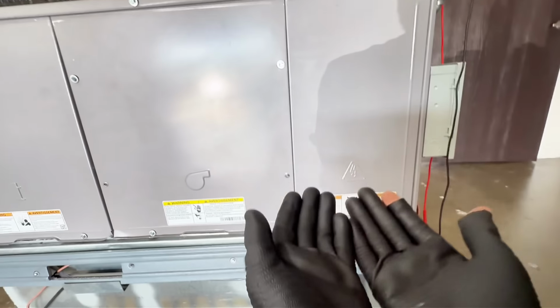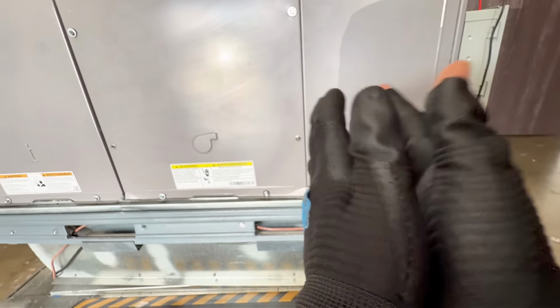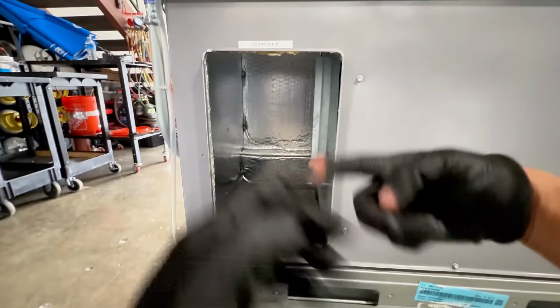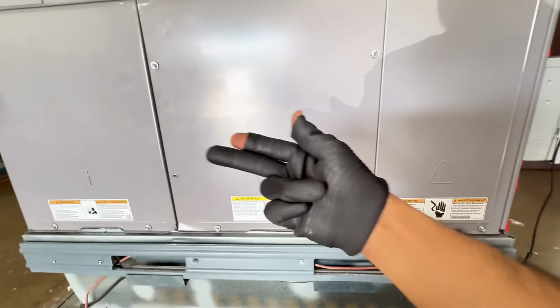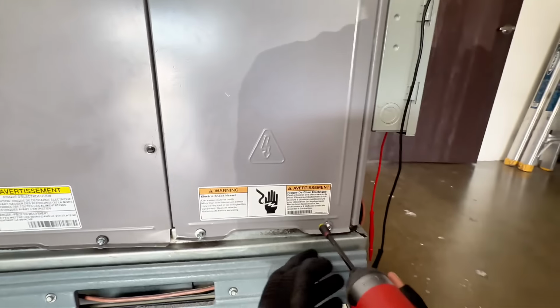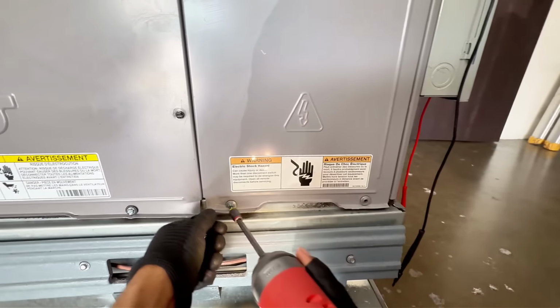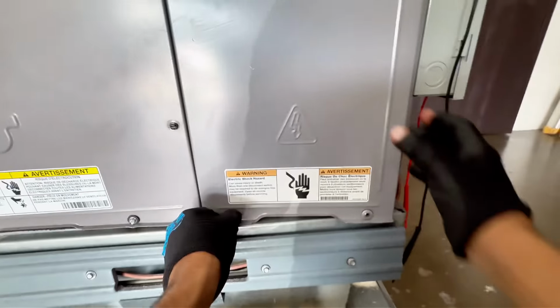So obviously we've been called because there's an issue, right? There's no cold air coming out. I did notice that I am getting air coming out, so my blower motor did turn on, which makes sense. Typically, the blower motor turns on, and you have about a 5-minute delay before the compressor turns on. So I'm gonna go ahead and open this up right here. Let's see what he did to the unit. Like I said, I have no idea.